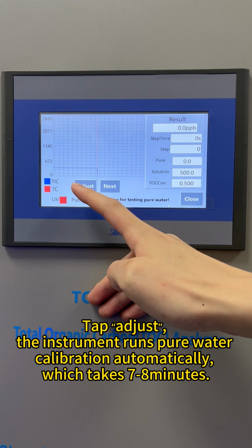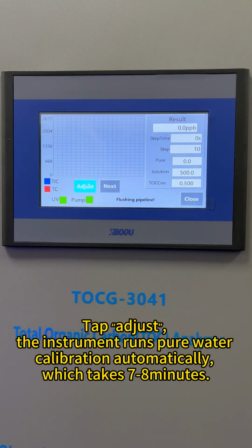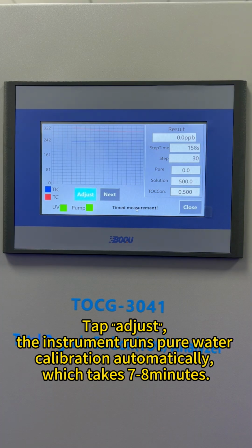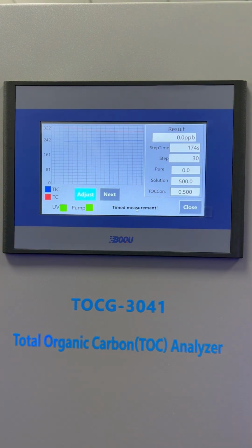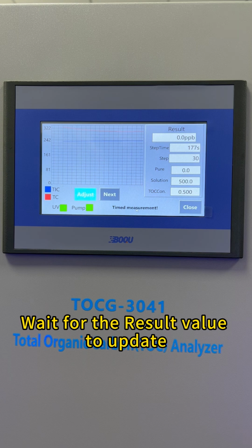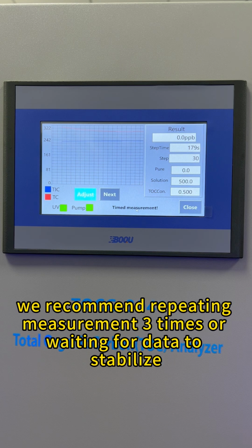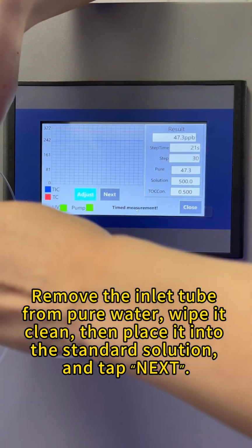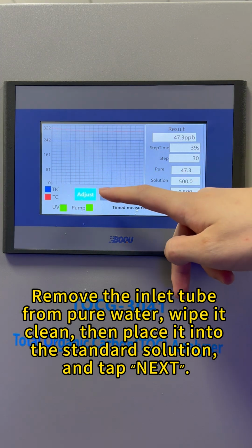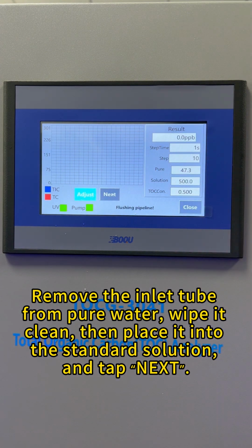Tap Adjust. The instrument runs pure water calibration automatically, which takes 7 to 8 minutes. Wait for the result value to update. We recommend repeating measurement 3 times or waiting for data to stabilize. Remove the inlet tube from pure water. Wipe it clean. Then place it into the standard solution and tap Next.